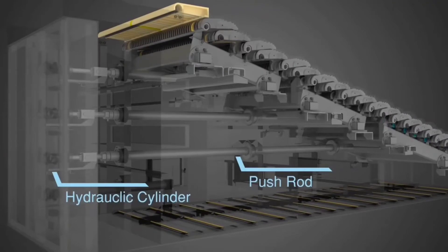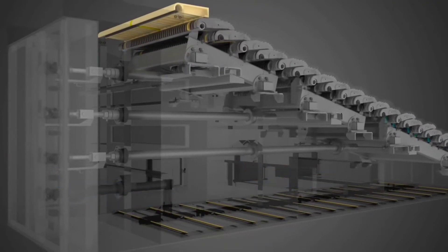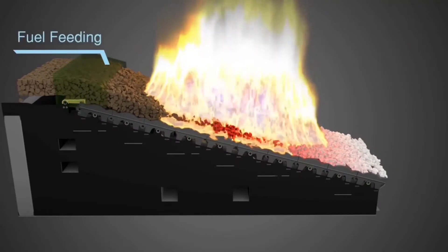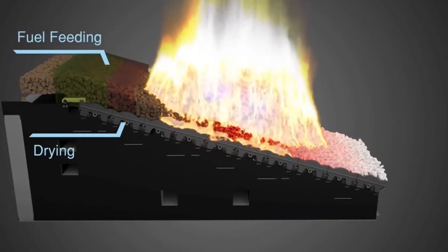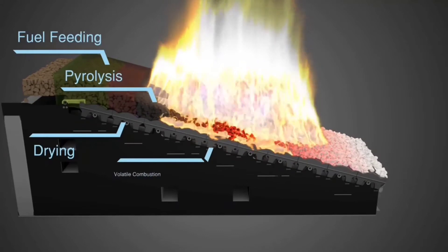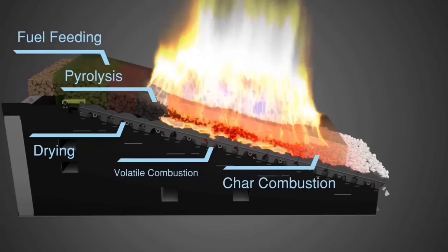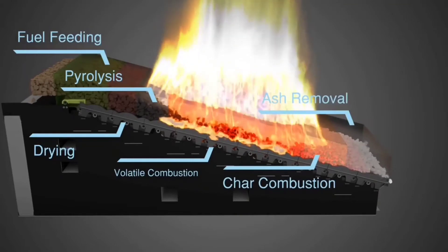Alternate movement of grate blocks pushes the fuel through distinct combustion zones of the grate: fuel feeding and drying, pyrolysis, volatile matter release, char combustion, and ash removal.